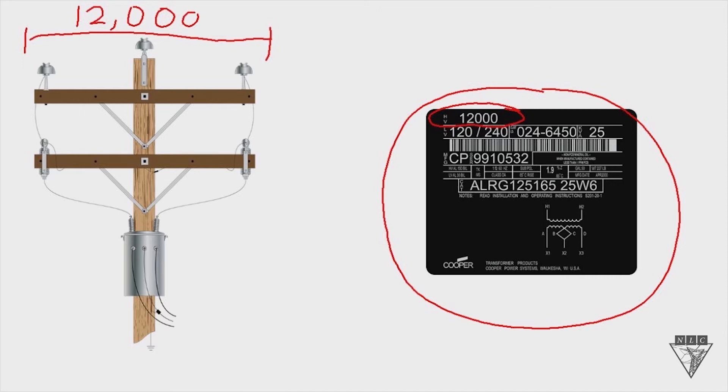Now, the important thing about the number, the 12,000 volts on your nameplate, that's what the insulation on the primary coil of the transformer is rated for. So if you go above 12,000 volts, you're going to damage the insulation of the transformer, and it's going to make it short circuit.